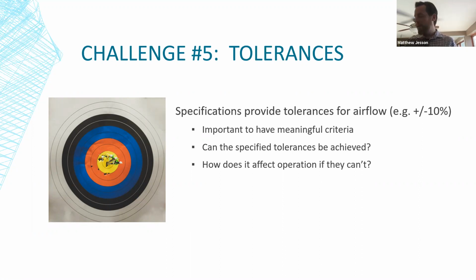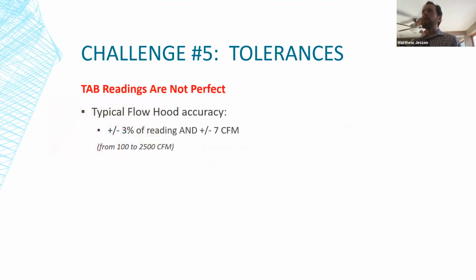But what I want to examine is, can the specified tolerances be achieved with the particular system that you have? And if not, then how's that going to affect operation? Is it a problem? So the important thing to note here is that TAB readings are just not perfect. Even when used properly, your flow hood accuracy is plus or minus 3% of the meter reading and plus or minus 7 CFM. And this is right out of one of the manufacturer's manuals. That is for a range from 100 to 2500 CFM.